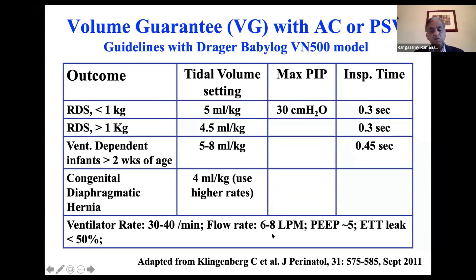Flow rate is 6 to 8 liters depending on the size of the endotracheal tube. ET tube leak will be displayed by the ventilator — try to keep it below 50%.